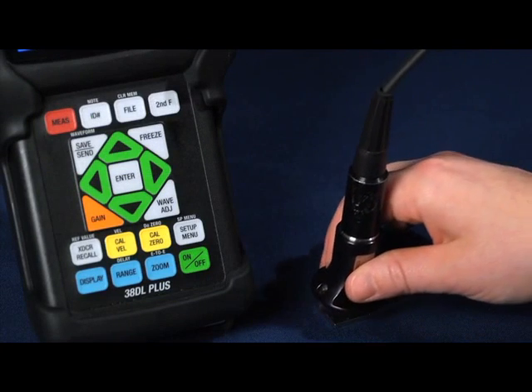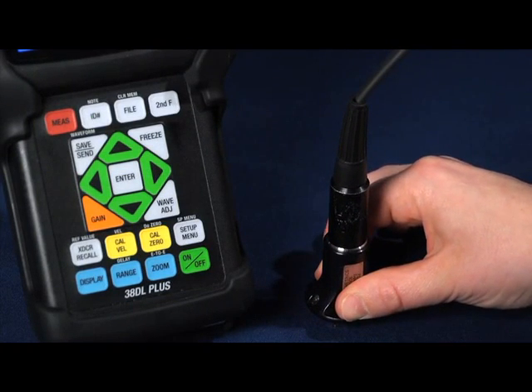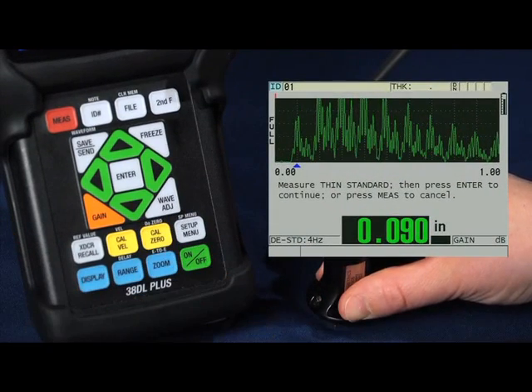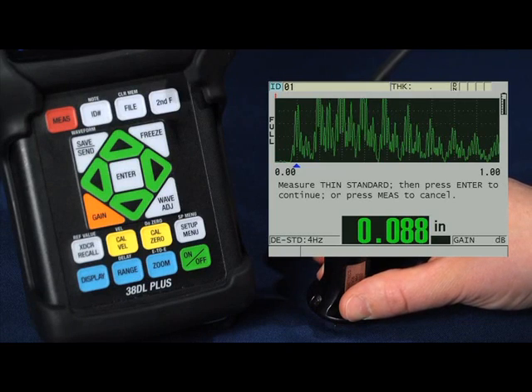Now you can proceed to your thin standard, the hundred thousandths step. Couple onto your thin standard and press the cal zero key. Once you have a steady reading, press the enter key.